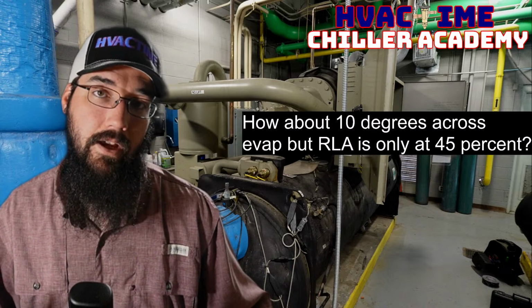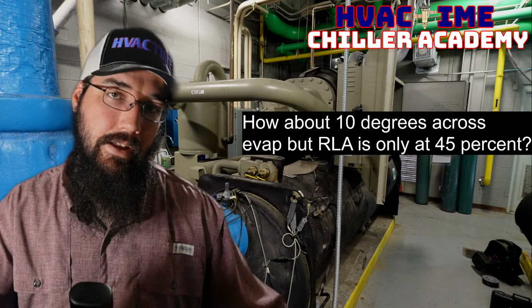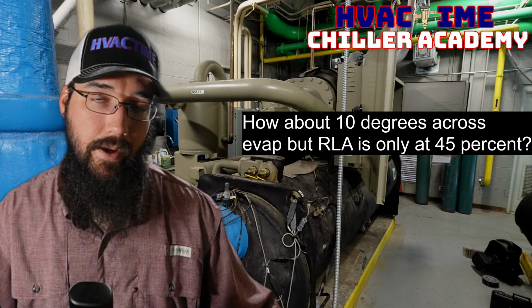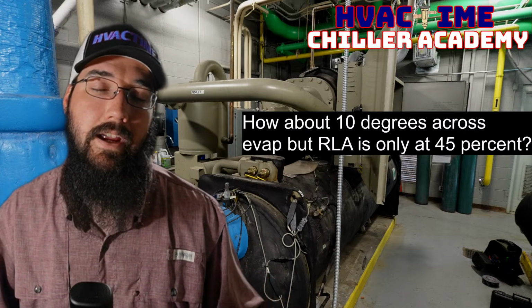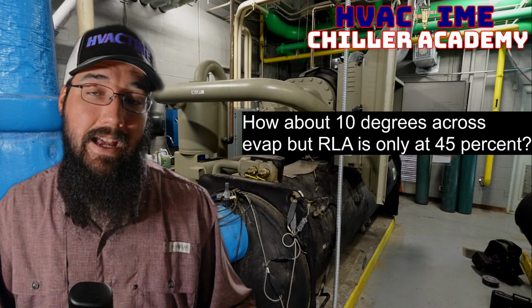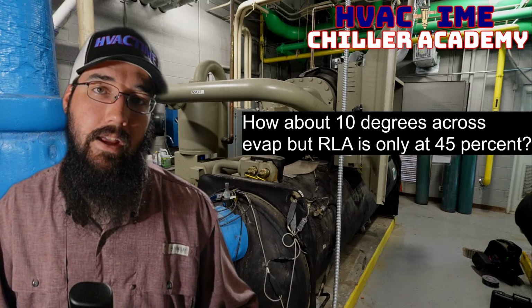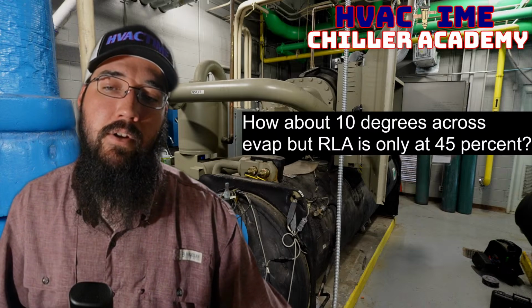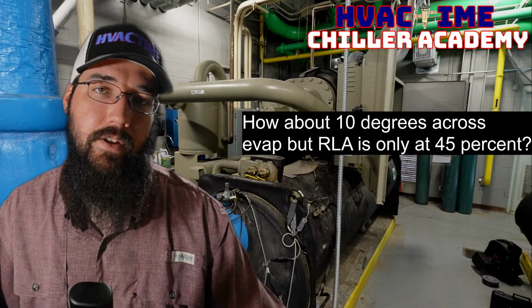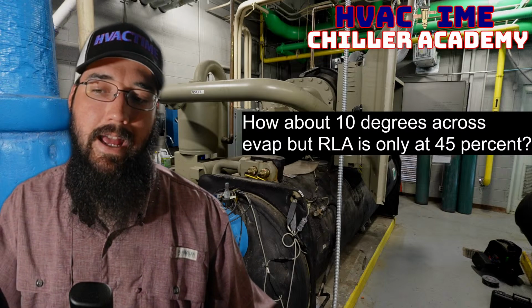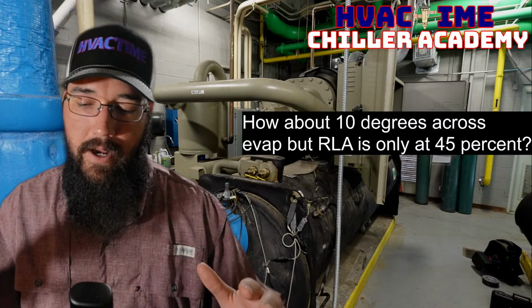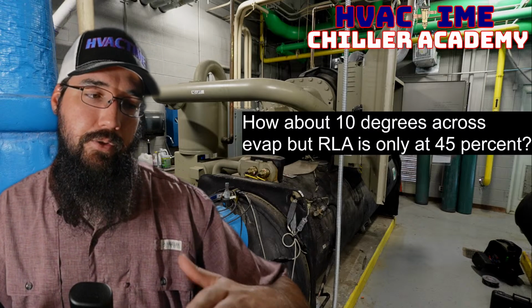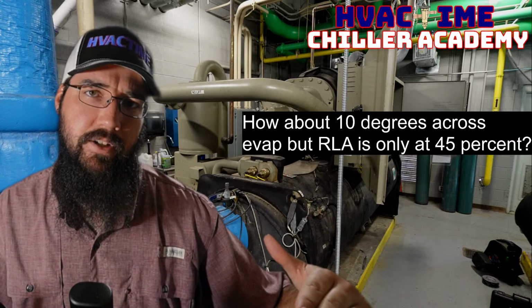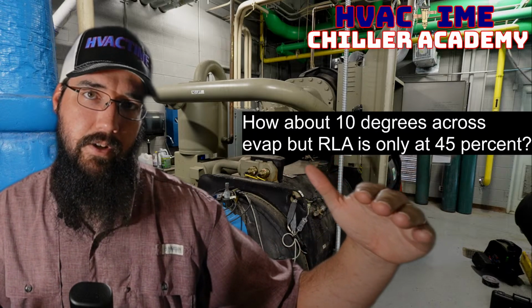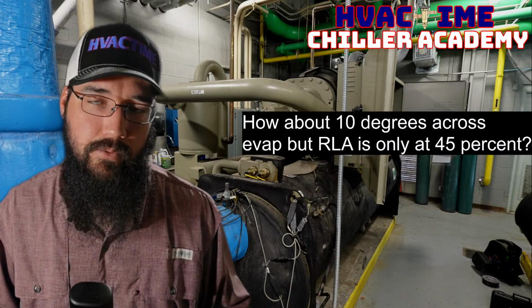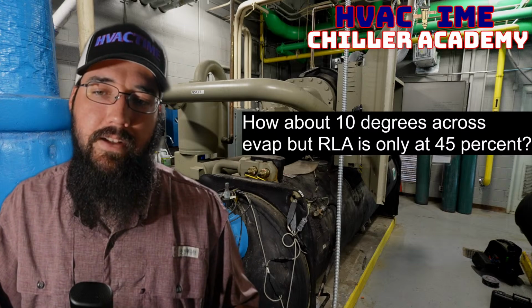And if you combine both of those together, where you've got a higher evaporator set point and a lower condenser water set point, the two of them are working together to lower the RLA the motor is going to have. So you could still have a technically loaded condition and GPM and all that be fine, but still have a very minimal load on the actual motor of the compressor. And it's just because we're not having to go as far with it. If you're having to compress from 45 degrees of saturation to, say, 70 degrees of saturation versus 45 degrees to 100 degrees of saturation, that is a major difference in how much work that compressor has to do. Major difference, which is going to be reflected in your RLA.